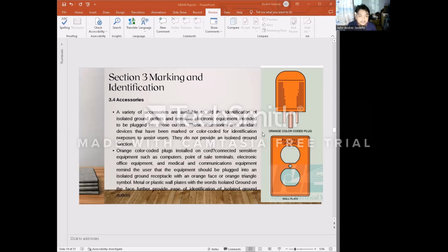Orange color coded plugs installed on cord connected sensitive equipment, such as computers, point of sale terminals, electronic office equipment, and medical communication equipment, remind the user that the equipment should be plugged into an isolated ground receptacle with an orange face or orange triangle symbol. Metal or plastic wall plates with the words isolated ground on the face further provide ease of identification of isolated ground outlets. Now these devices need to be labeled, or the color of their plug needs to be orange, so they can be plugged into isolated ground outlets, which you can see have an orange wall plate with the words isolated ground written on it.